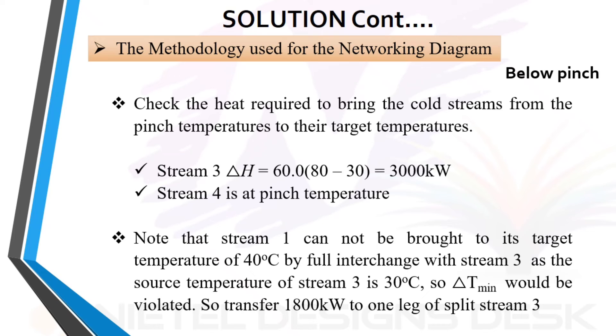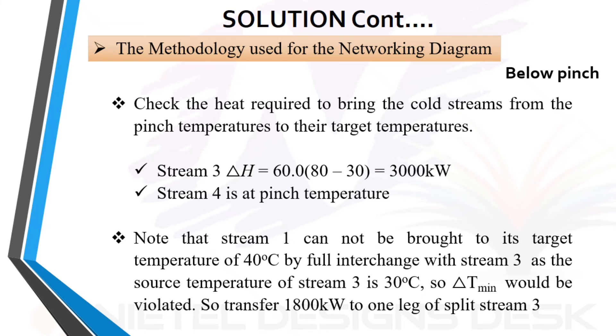Stream 4 is at pinch temperature. Note that stream 1 cannot be brought to its target temperature of 40 degrees Celsius by full interchange with stream 3, as the source temperature of stream 3 is 30 degrees Celsius, so the minimum temperature difference would be violated. Therefore, transfer 1800 kilowatts to one leg of the split stream 3.